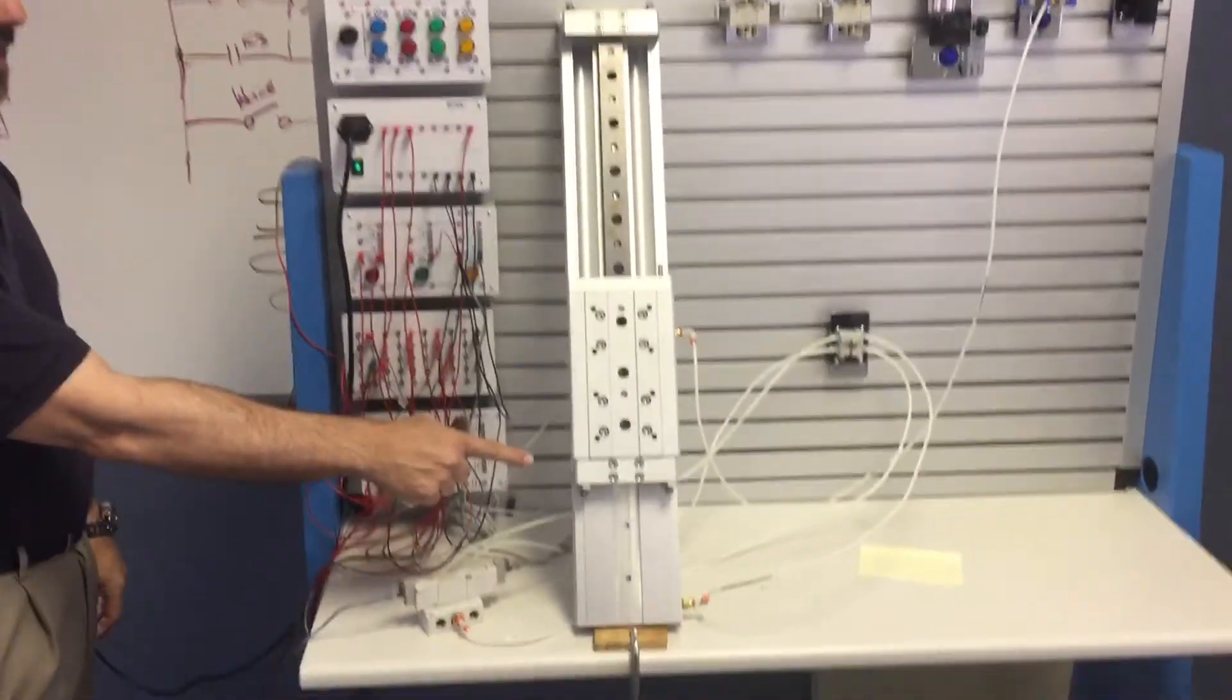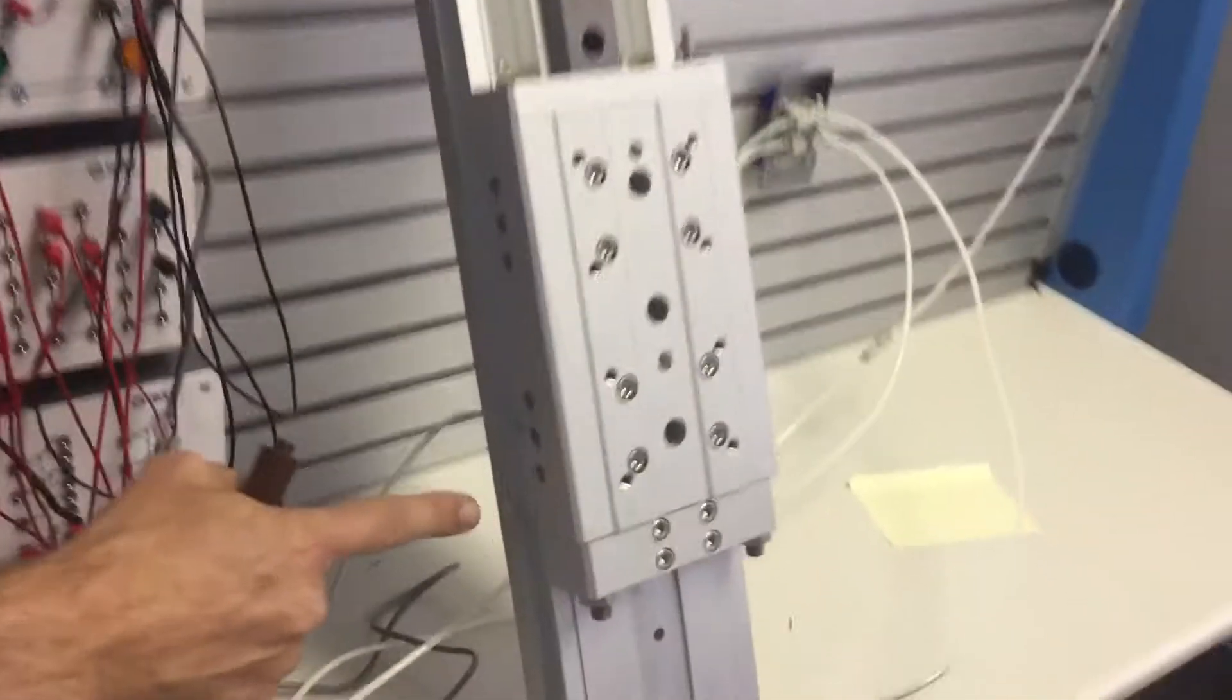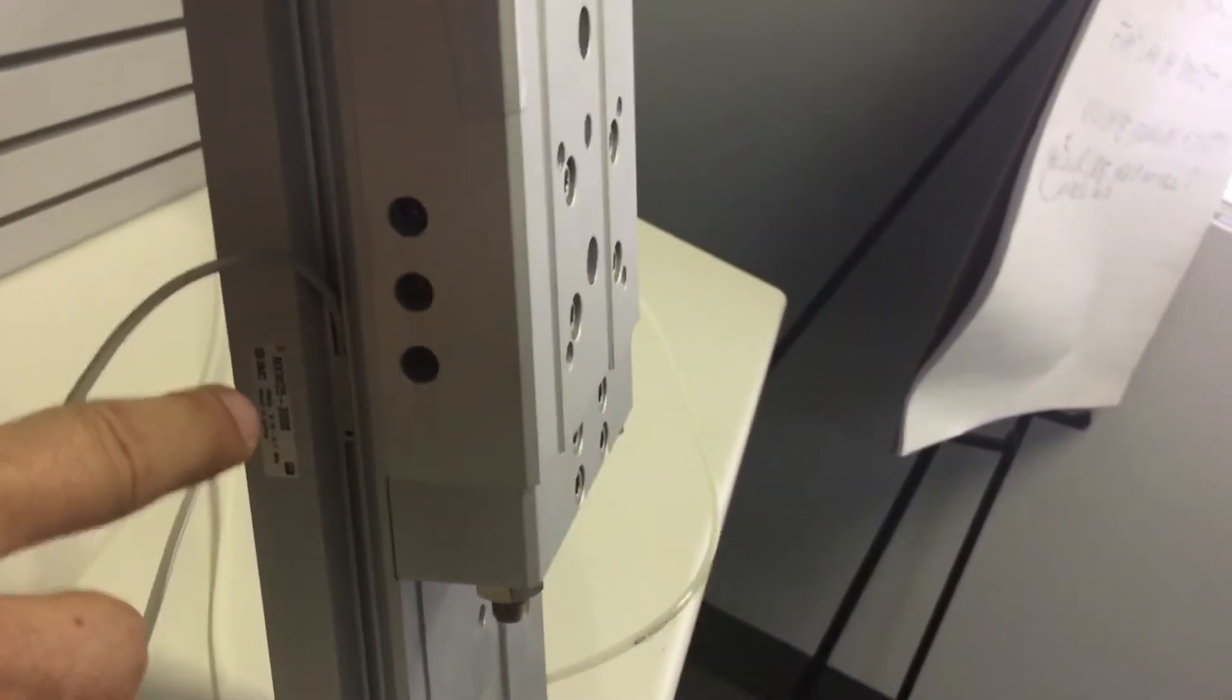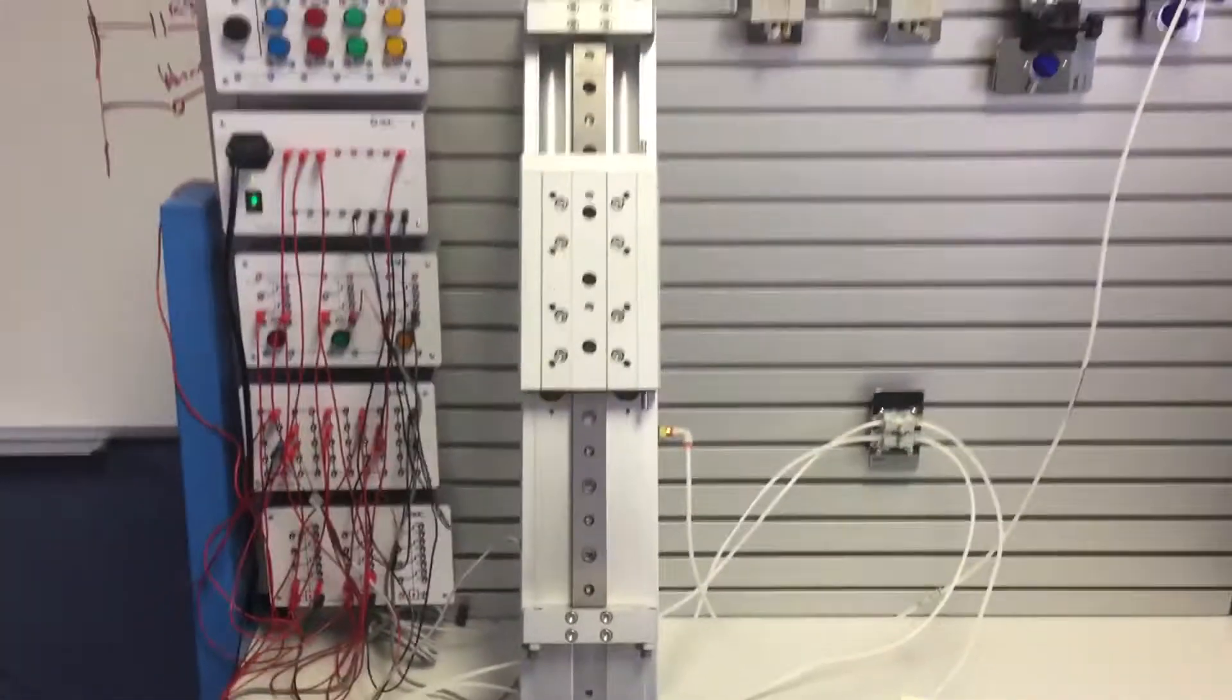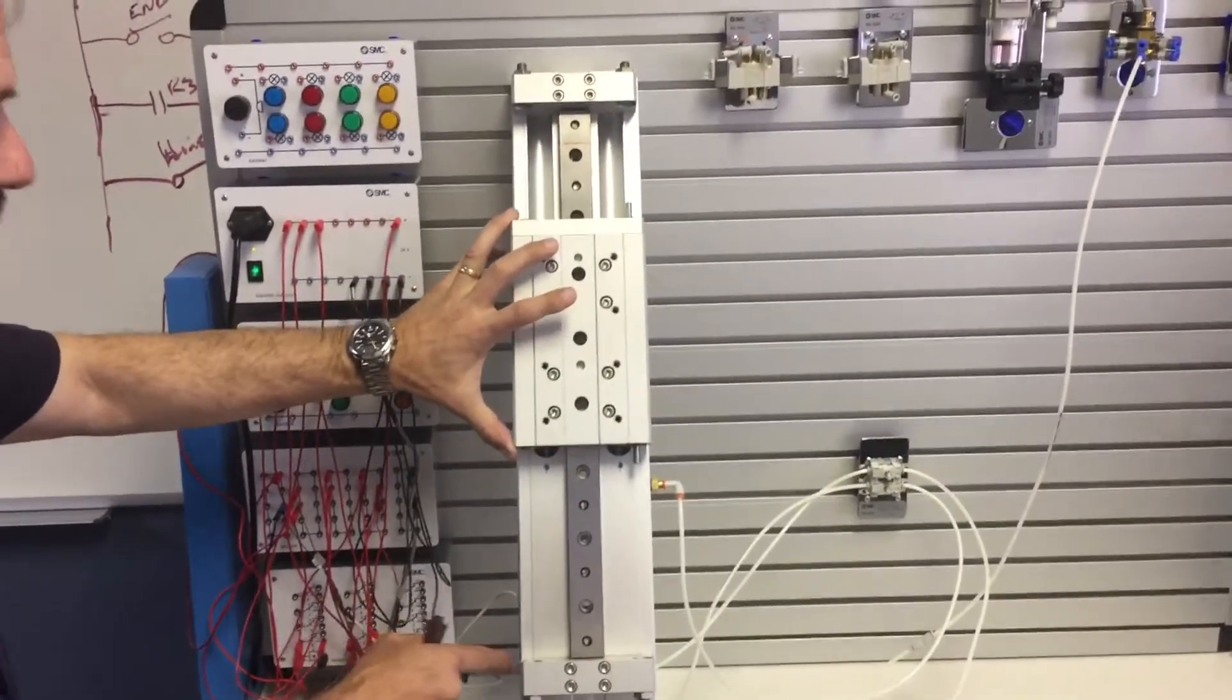I'm going to pan on the auto switch. Here's the auto switch we're using to trigger the stop. I'm going to enable the circuit and do an intermediate stop. As you can see, it stops when it hits the sensor and trips the valve here.